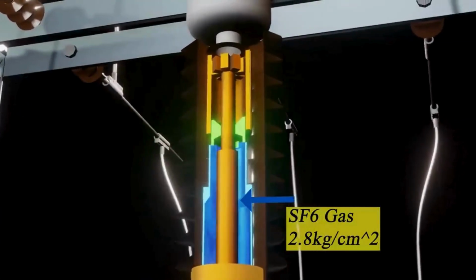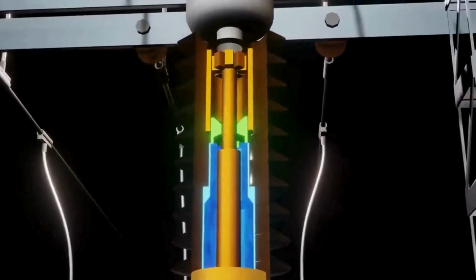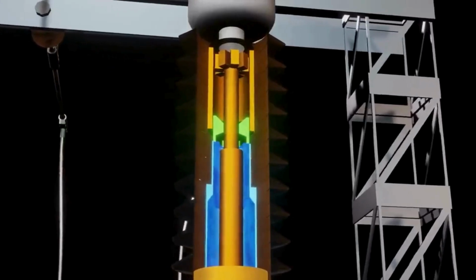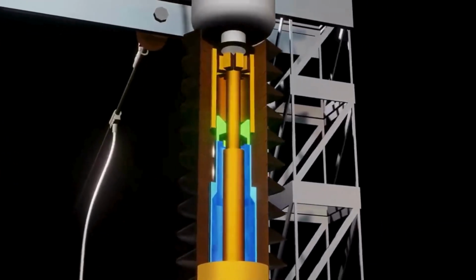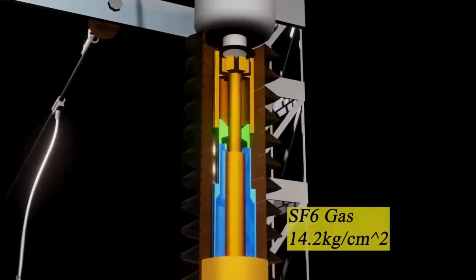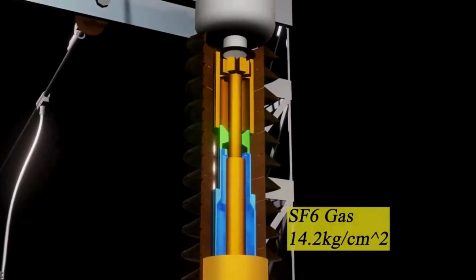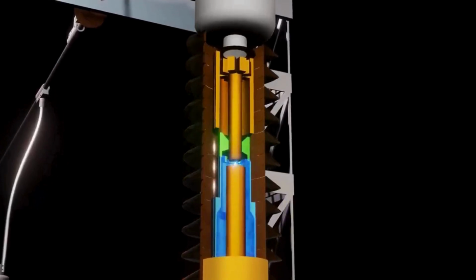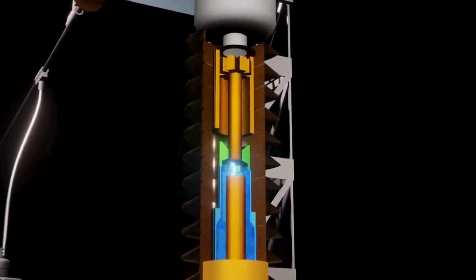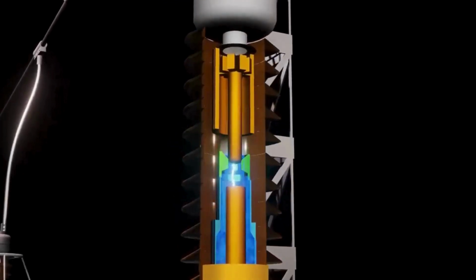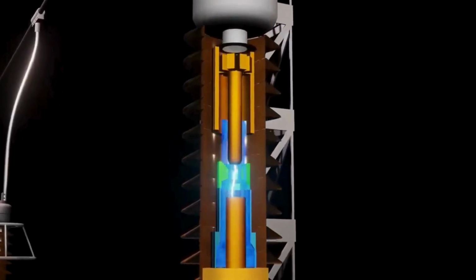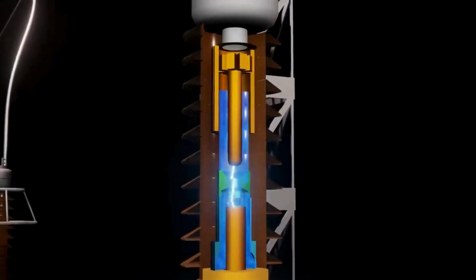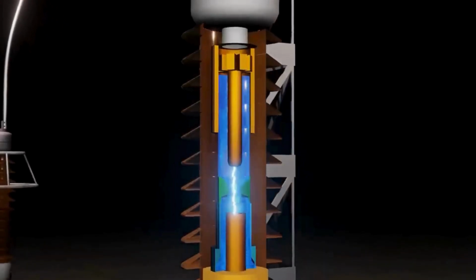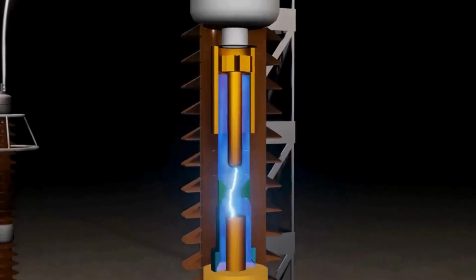So along with this rod, the cylinder attached here will go down, but there is a piston in the cylinder which is absolutely fixed. And there is SF6 gas between this cylinder and the piston, at a pressure of 14.2 kilograms per cm2. As soon as these contacts move away from each other, a tremendous arc will be generated, but the piston will increase the pressure of the gas so much that the SF6 gas will come between these two contacts.